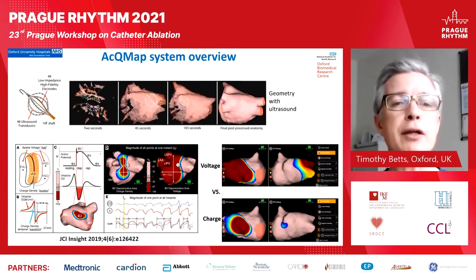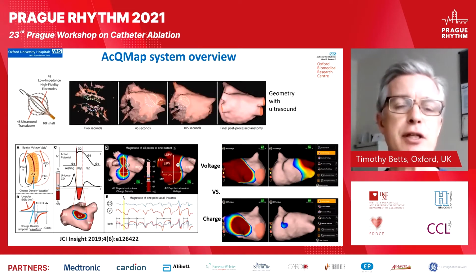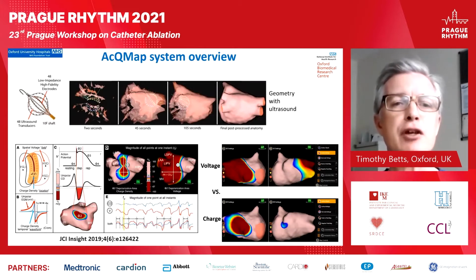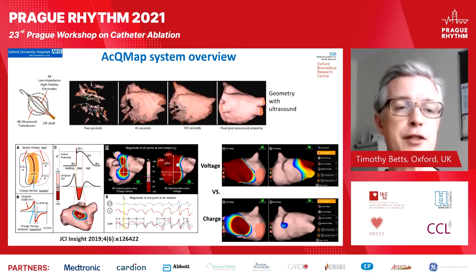So step 1 is to create chamber geometry by gently rotating the basket inside the left atrium in this example, collecting over 100,000 points per minute. A whole chamber geometry normally just takes 1 or 2 minutes to collect, and then a little bit of post-processing. The other novel aspect is the non-contact mapping itself. And this is where the 48 electrodes sit in the center of the cavity and detect unipolar far-field voltages.